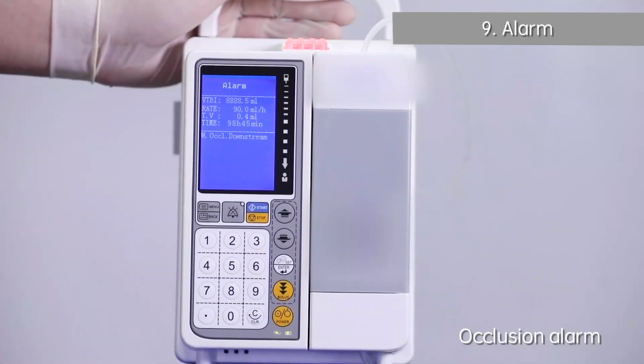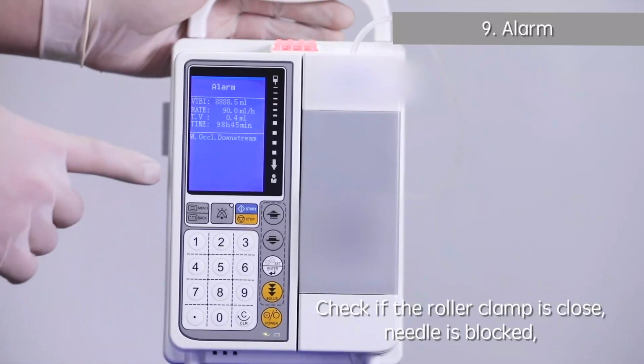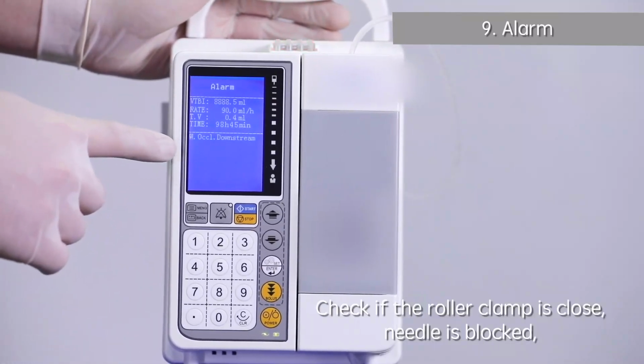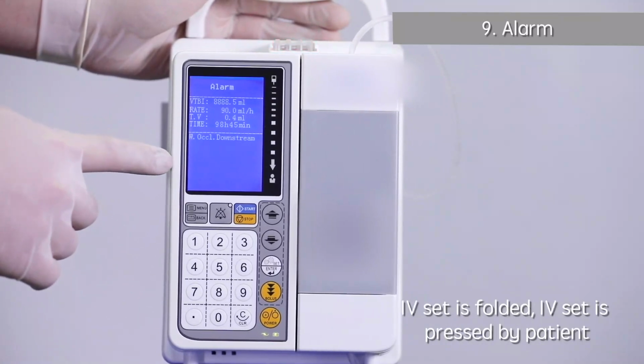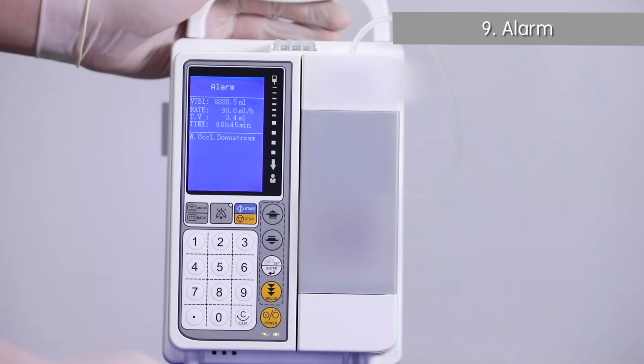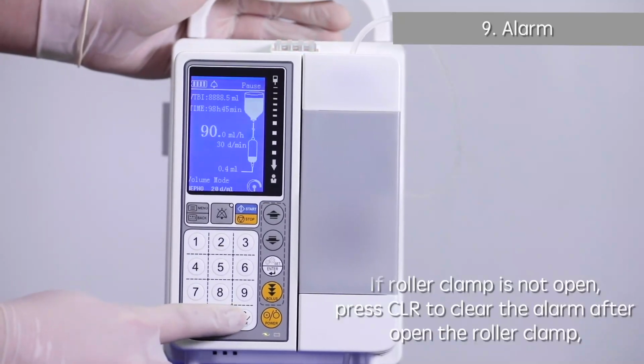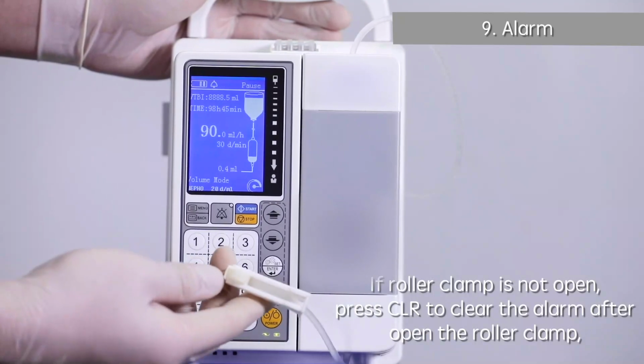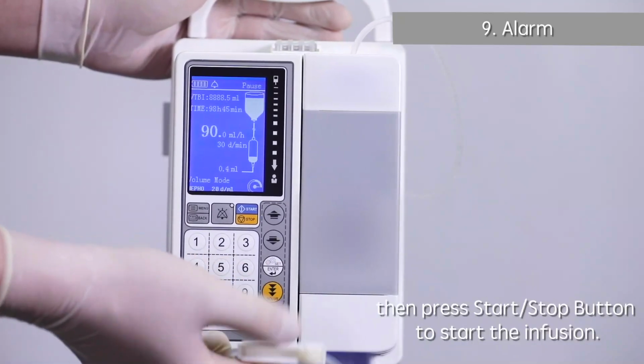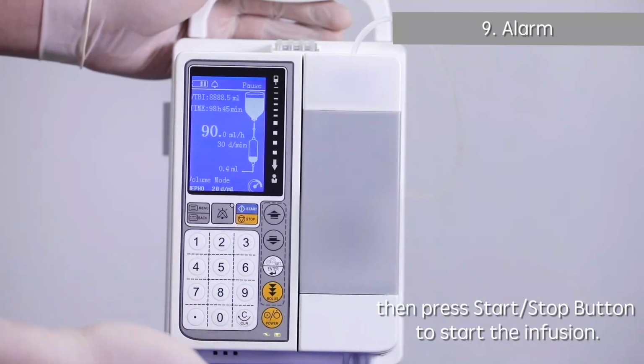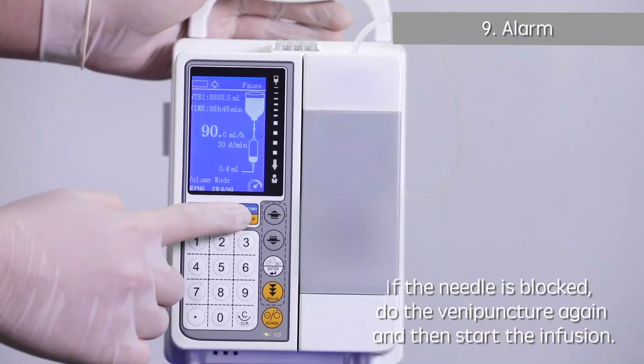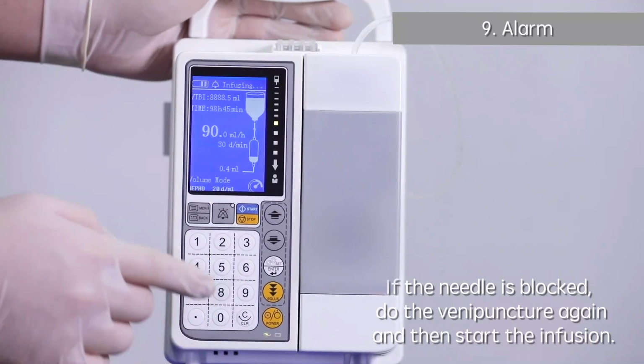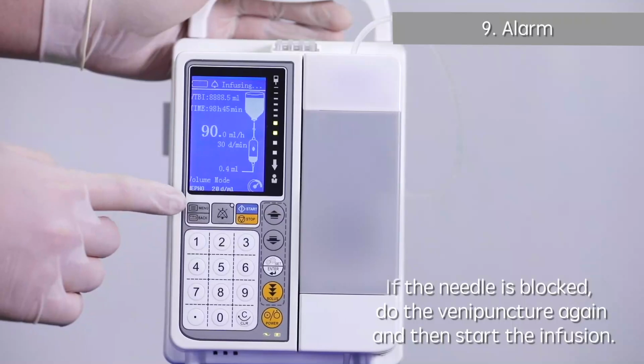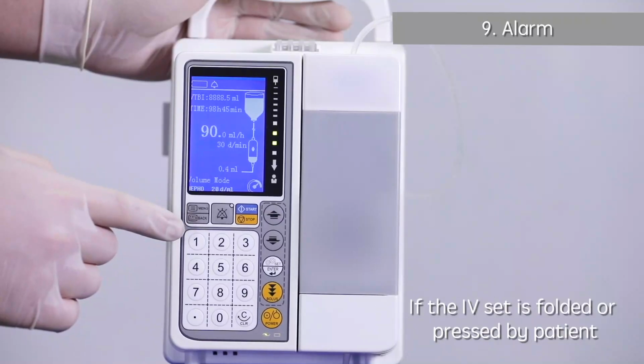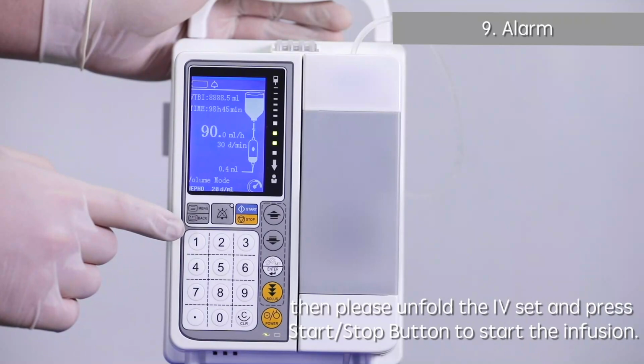2. Occlusion alarm. Check if the roller clamp is closed, the needle is blocked, the IV set is folded, or the IV set is pressed by the patient. If the roller clamp is not open, press CLR to clear the alarm after opening the roller clamp. Then, press Start/Stop button to start the infusion. If the needle is blocked, do the venipuncture again and then start the infusion.